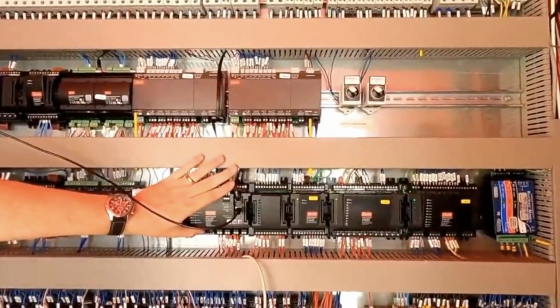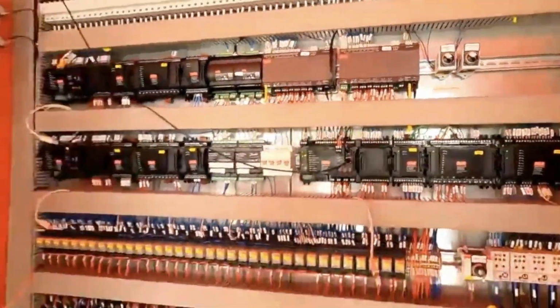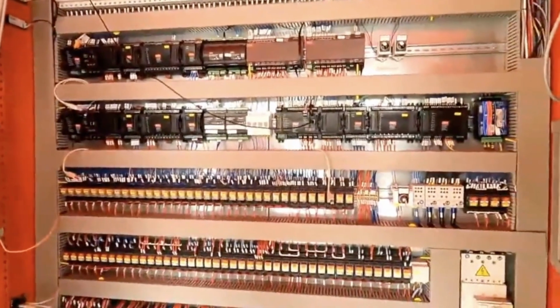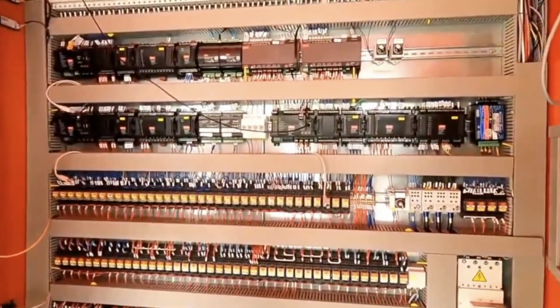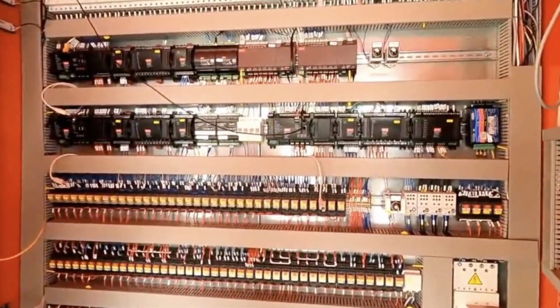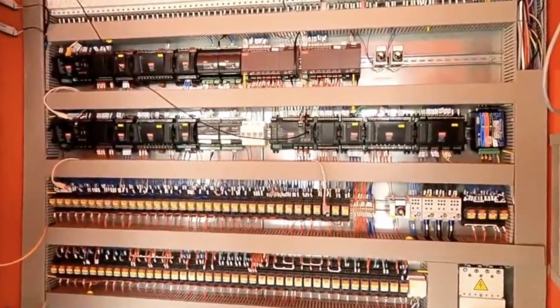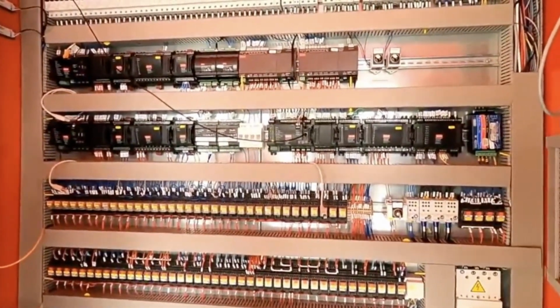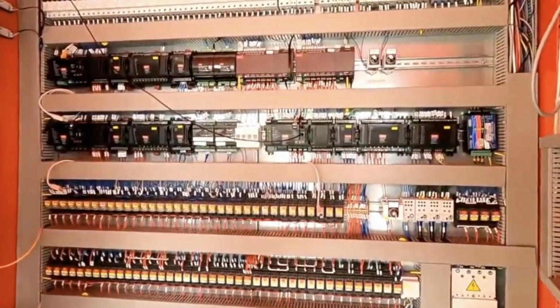multi-ejector high pressure ejectors. And then the balance of the components, again, to make the point, I don't want anyone to have sticker shock that you need all of this because it's transcritical. For the system that we have, you'd have about 1/4 of what you see here in your control panel. So it'd be a much smaller control panel.